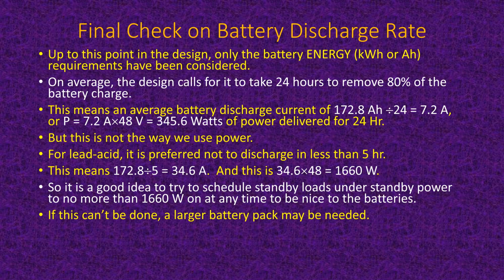The system I worked on this morning used 2 battery packs at 10 kilowatt hours each. So that means they take advantage of them and get double the power rating to feed, and now they can feed loads on a 40 amp circuit breaker rather than just a 20 amp.